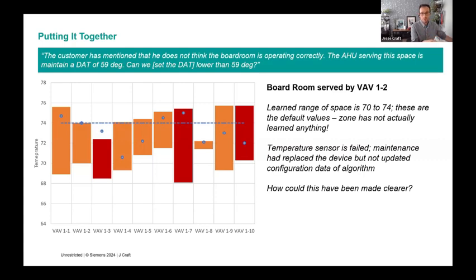And note that many fault detection systems only look at point values and not at what I would call point metadata, like status and priority. It also didn't show up on the graphics because a virtual point was on the graphics instead of the actual sensor point, and the virtual point wasn't failed. So nobody noticed.